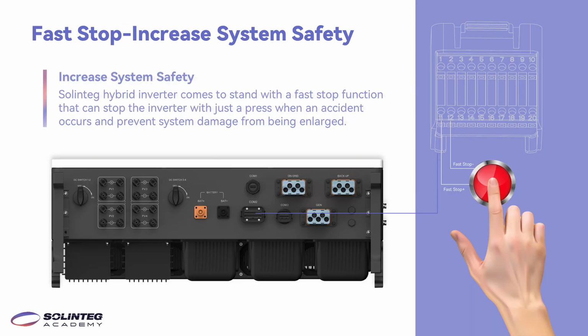Solinteg Hybrid Inverter has a function of fast stop. Fast stop means that you can stop the inverter's connection, including the AC side, the solar panels and the battery, quickly with just a push button. Without this function, if you want to stop an inverter, it may take you 1 to 3 minutes to turn off the AC switch and the DC switch of the battery and solar panels. But with this function, you can stop the inverter with just a press when an accident occurs, prevent the system damage from becoming large, and it is safe when you do the maintenance.